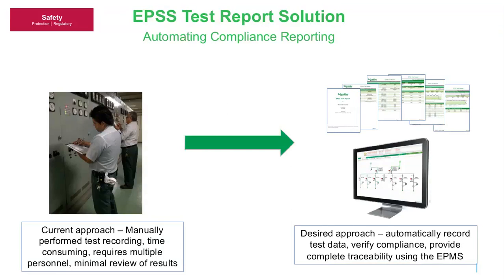So currently, or maybe for some in the past, but still for many, the manual method is used. A technician or multiple technicians are taking values, going to equipment, checking, making sure everything works right, but mostly making sure they've documented that monthly test. All of that, utilizing the monitoring system, can now be automatically collected, automatically stored and put into reporting, and then it can be verified to make sure that it's following all of the right standards and is compliant.